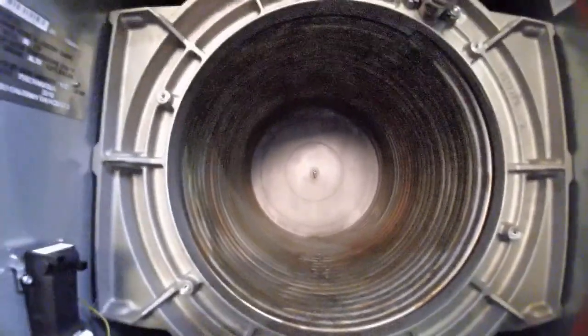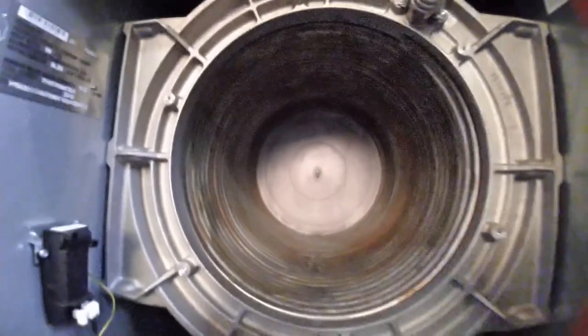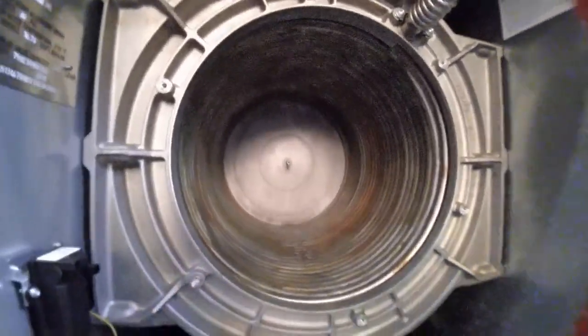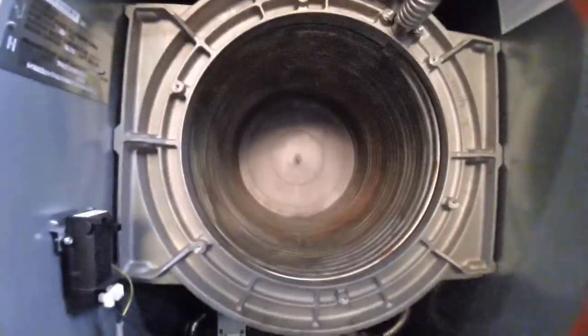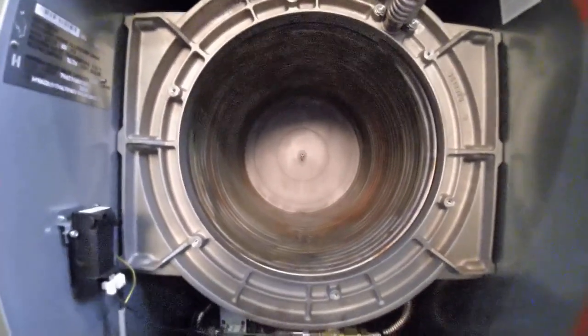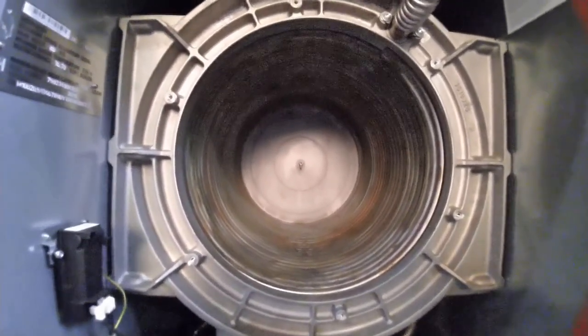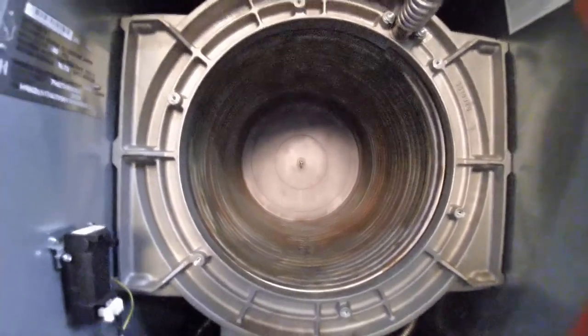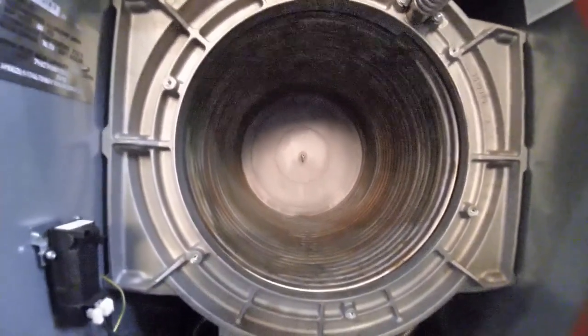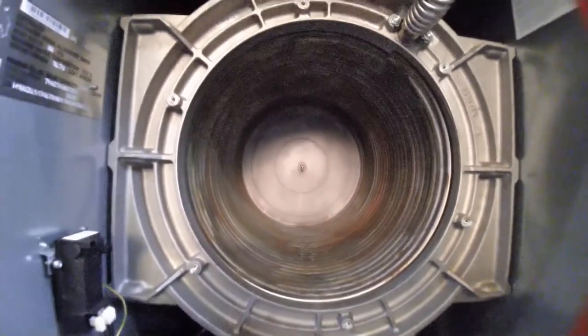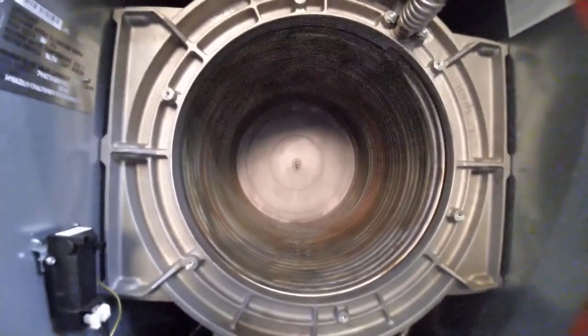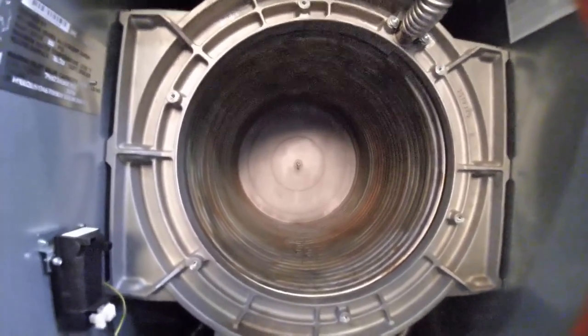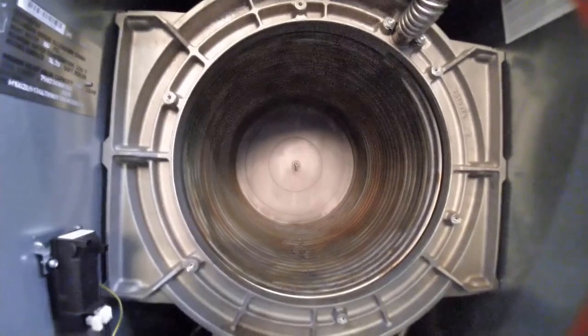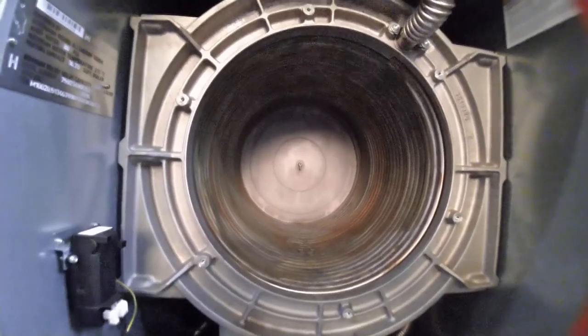We just recently cleaned a couple of Weil-McLain Ultra boilers. They had much different style heat exchangers than these. They're constructed of aluminum, and they were plug solid. Somebody was making a half-hearted attempt to clean them with a piece of brazing rod and a hacksaw blade. So we purchased the proper tools, and actually took about 2.5 hours on one boiler to clean it out, but it's now functioning normally again.